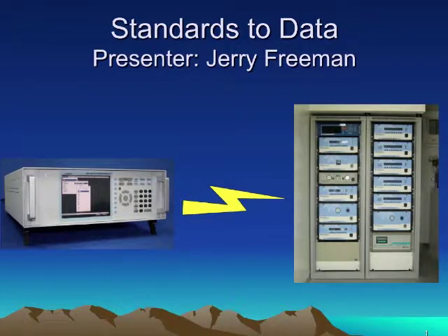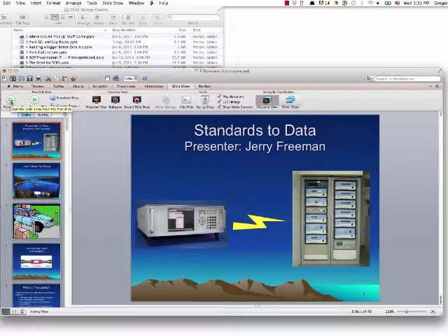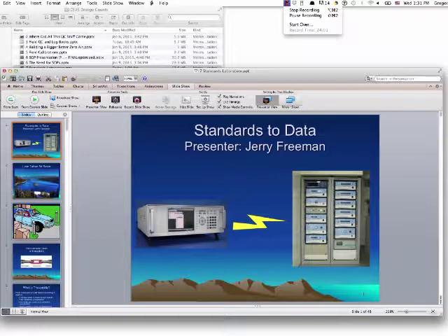So that's why, because of that variation, instead of just using whatever it's set to run at, we take the value of the next 3 days, and the average of that becomes our expected values that we're expecting to see on our nightly checks. Then is your expected value still to fall within that 7%, or do you give leeway to the expected value versus the standard value that you just calibrated with? We use the expected value as the true value. So we would look at percent difference from that.